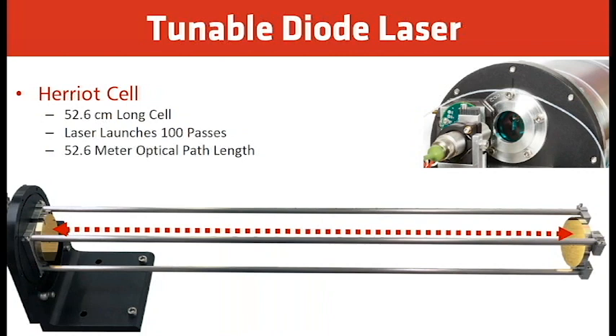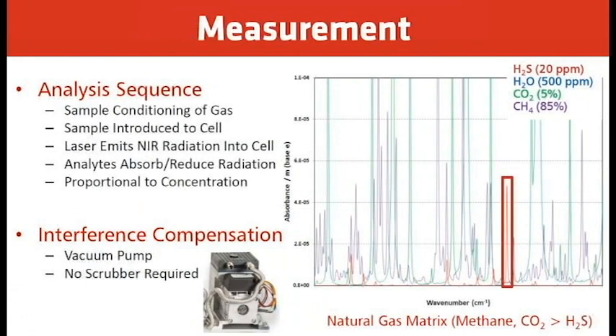All right. So for the analysis, we start by extracting the sample or the gas using a sample probe. Then we filter that sample for any particulates or any liquids to make sure that we get rid of those. The pressure gets regulated. The sample passes through the cell, which I just showed you. The H2S absorbs that light. And from that absorbance, again, the analyzer can calculate the concentration of the H2S. Same thing, of course, applies to any other component we are interested in measuring here.